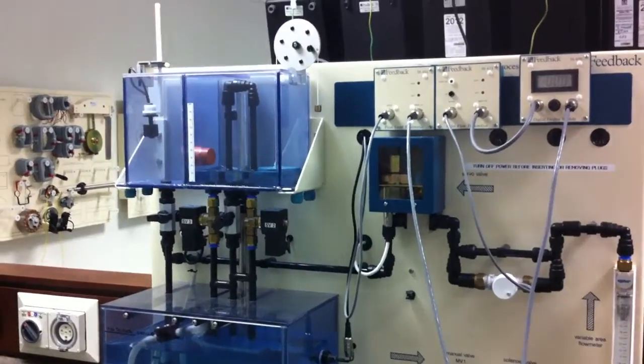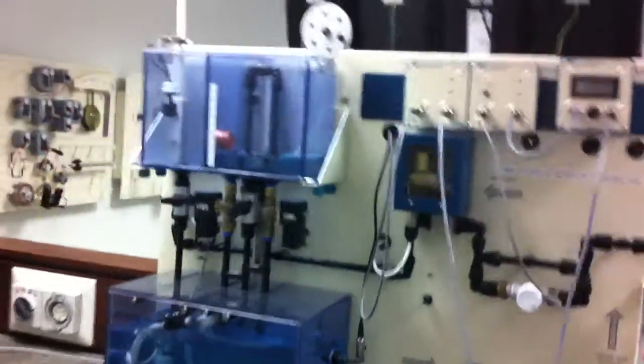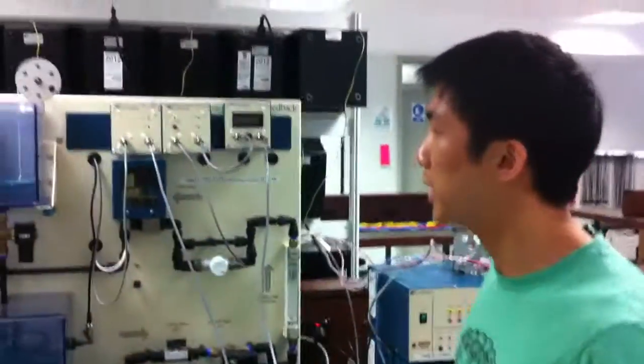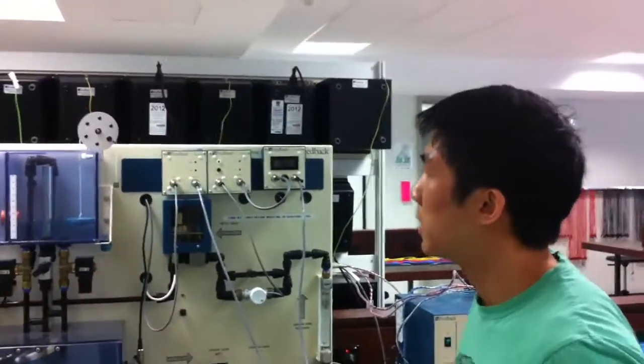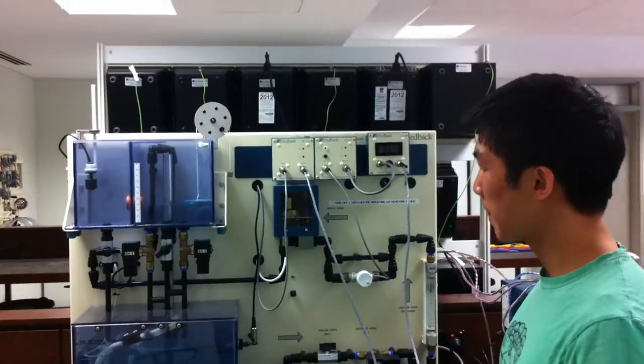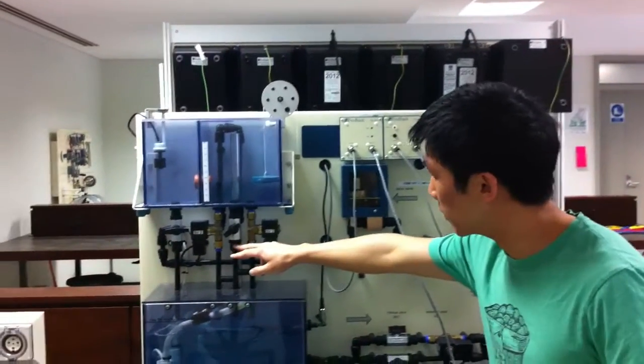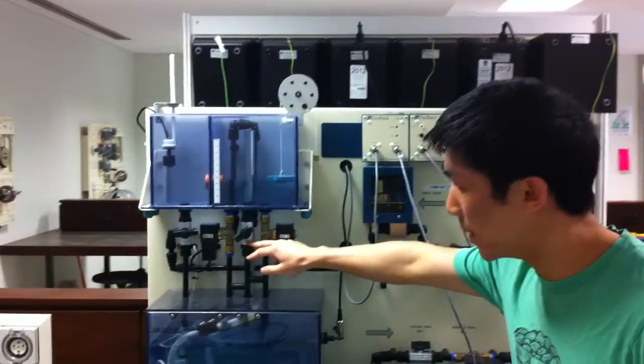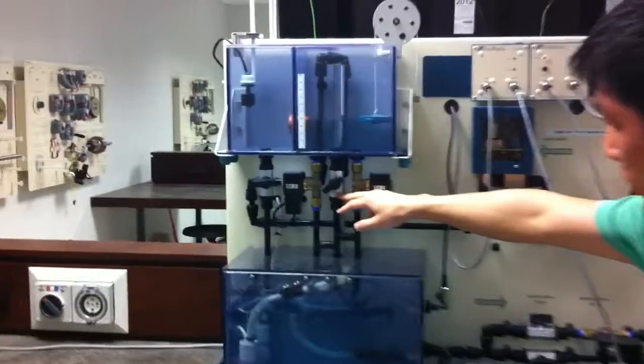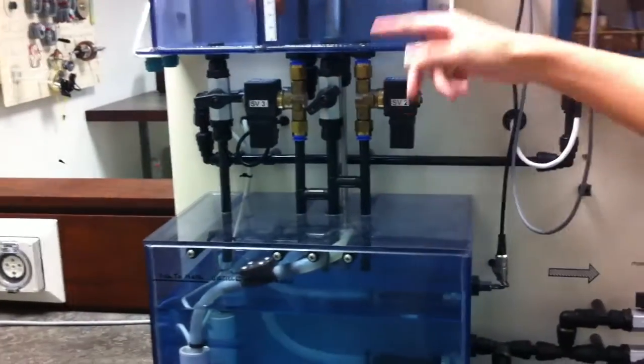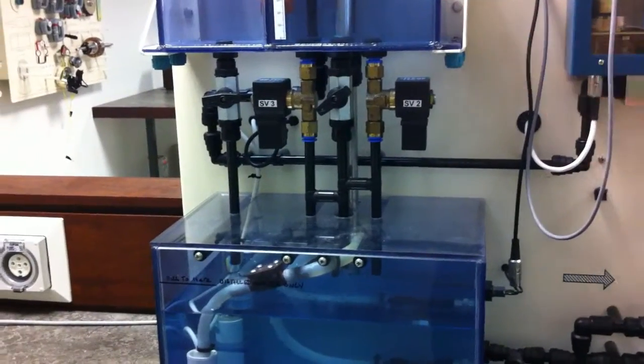The same as before, we're using the solenoids and the servo to control the water level. The set point is 50% once again. In this case, we've opened the manual valve, so there's a constant flow of water out of the process tank.